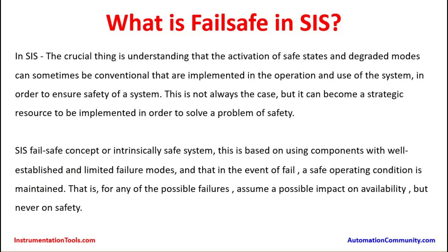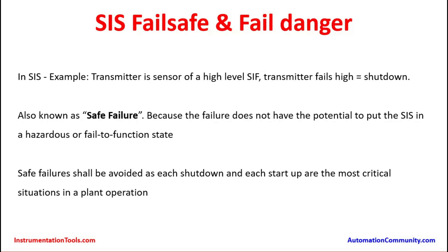The SIS fail safe concept, also known as intrinsically safe system, is based on using components with well-established and limited failure modes such that in the event of a failure, a safe operating condition is maintained — impacting availability but never safety. For example, a transmitter used as a sensor for a high-level safety instrumented function that fails high will trigger a shutdown. This is known as a safe failure because the failure does not have potential to put SIS in a hazardous or fail-to-function state.